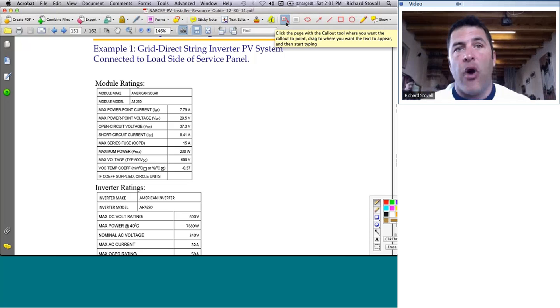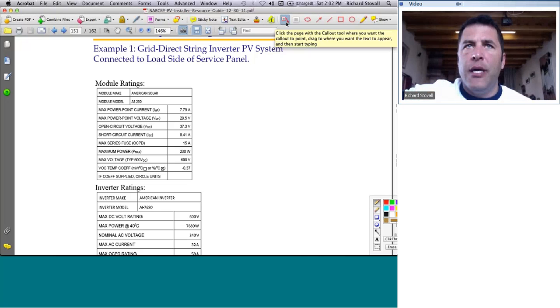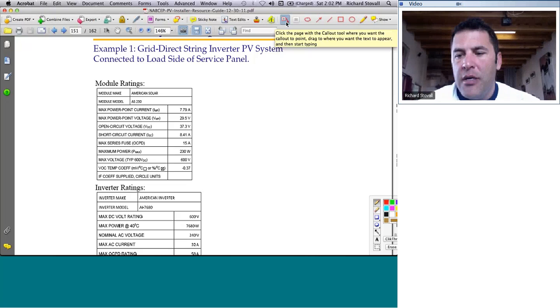And furthermore, because it's got such a broad range and two MPPT inputs, you can start an Aurora system with as few as 5 60-cell modules in series. Okay, and that's 230 watt modules in series, 1.2 kW, and then expand it over time up to as much as 3,500 watts to 3,750. It's got a 3,000 watt AC output. So the power going in, I believe, is a maximum recommended at 3,750. So it has all or many of the advantages of a microinverter system, but it's done in a centralized inverter way.